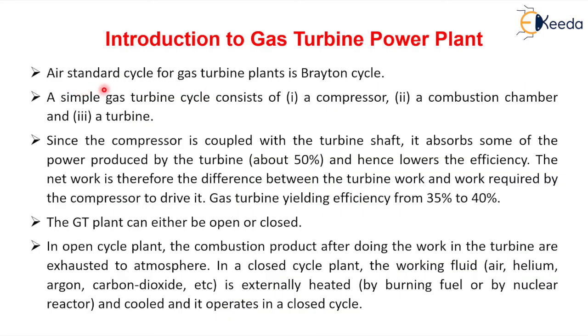The air standard cycle for Gas Turbine Power Plant is the Brayton cycle — you have to remember this. A simple Gas Turbine cycle consists of a compressor, combustion chamber, and a turbine. Since the compressor is coupled with the turbine shaft, it absorbs some of the power produced by the turbine — approximately 50%. The net work is therefore the difference between the turbine work and the work required by the compressor to drive it.